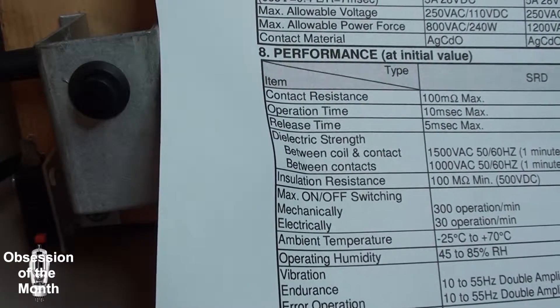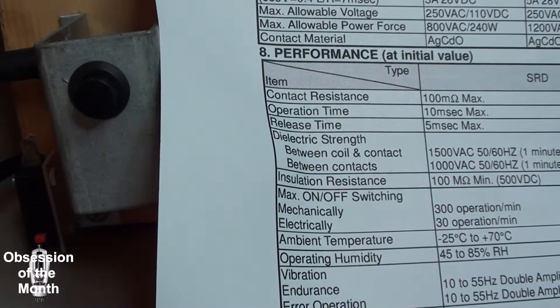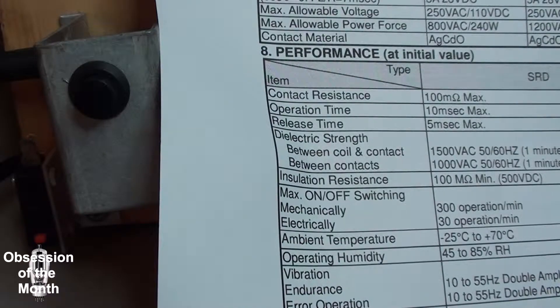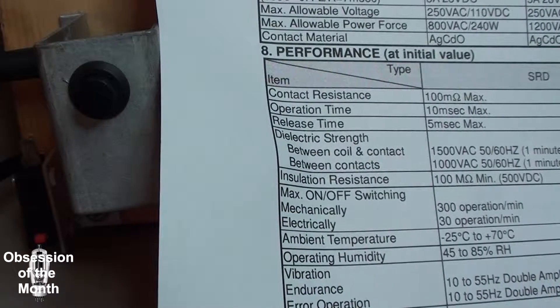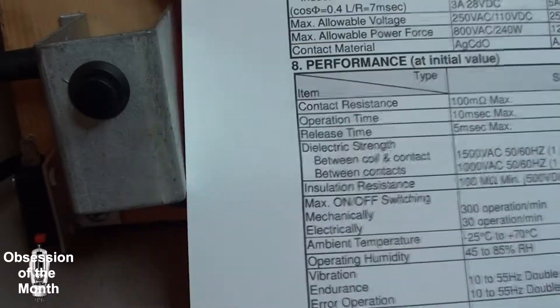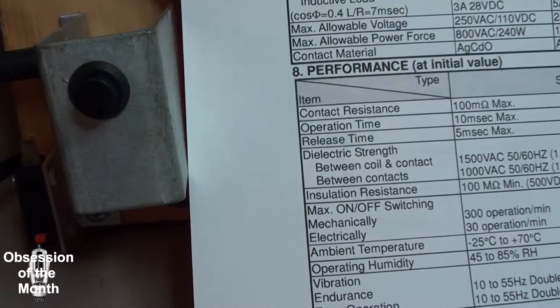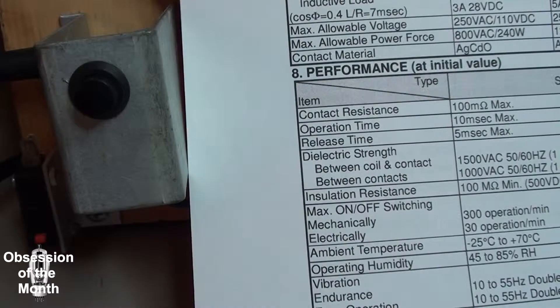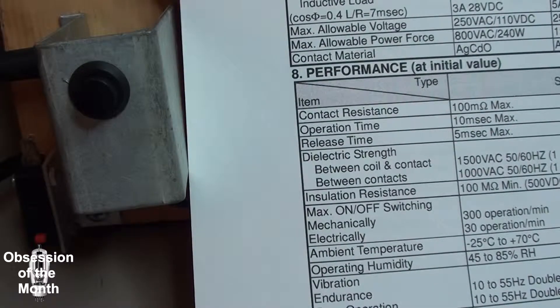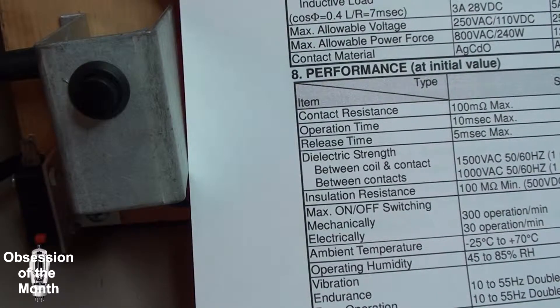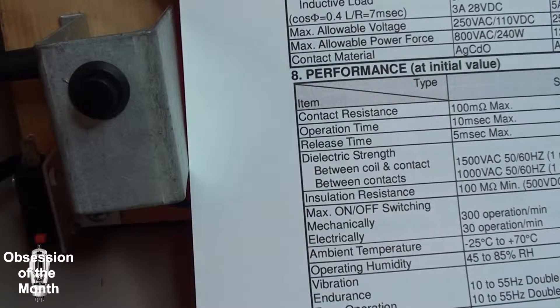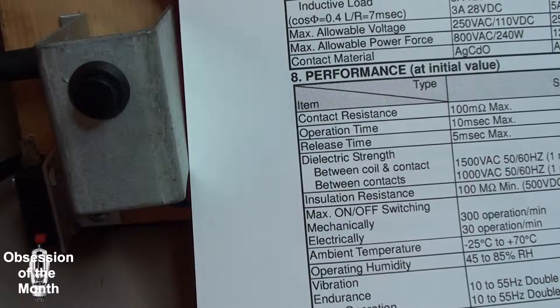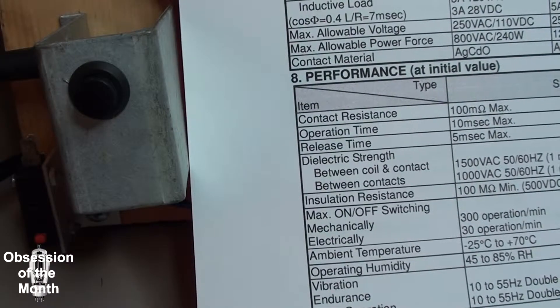That's an indication of the minimum time that you can energize the relay, or the way it engages and then disengages. So it takes 10 m seconds to engage, 5 m seconds to disengage.